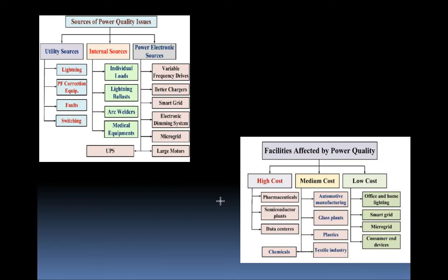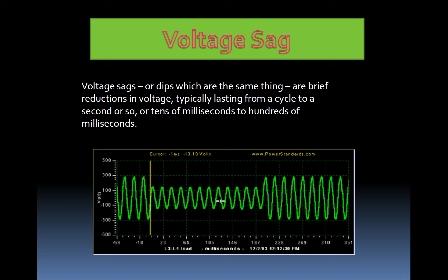We have to learn about voltage sag, also called voltage dip, meaning a reduction in voltage. It can last from 1 cycle, or 2 seconds, or milliseconds, or 100 milliseconds, depending on the severity of each incident. Voltage sag is caused by disturbances, non zero impedance faults that increase the current and affect the voltage. But these reductions are usually small enough to stay within voltage tolerance, maybe plus 10 minus 6 percent, so it can be maintained.